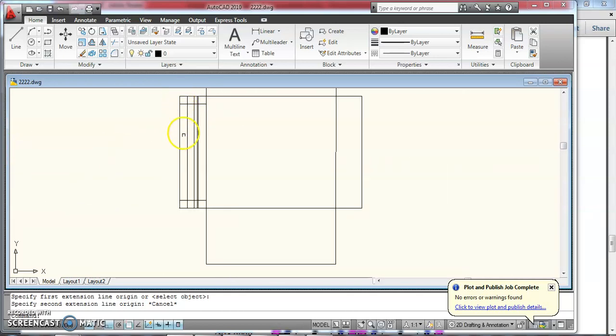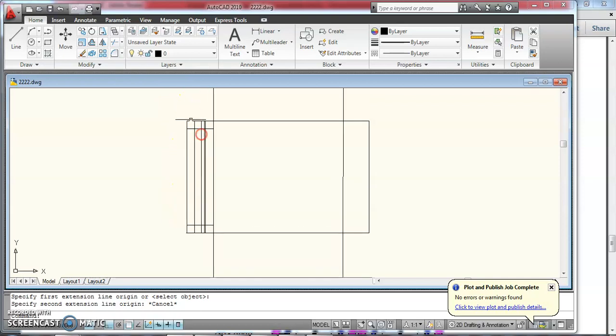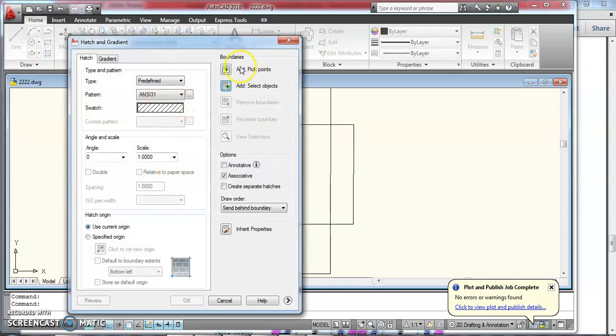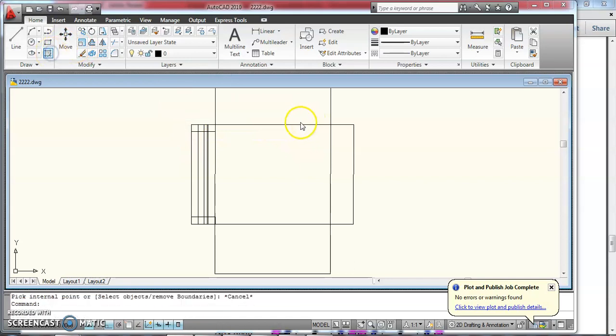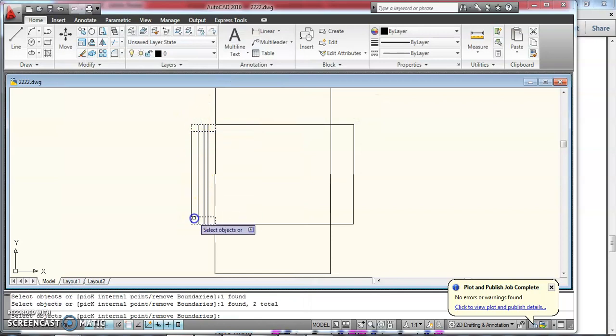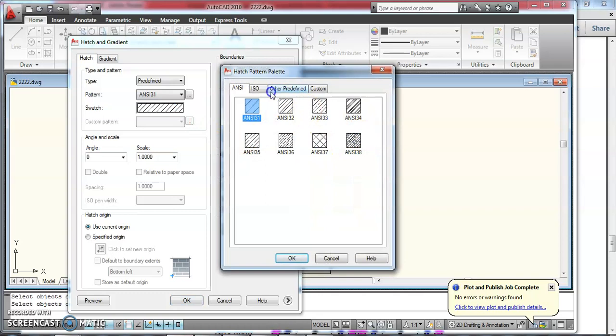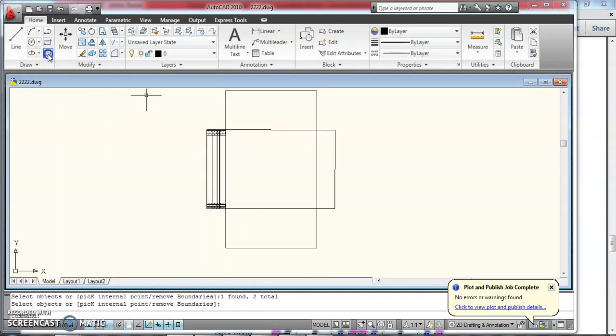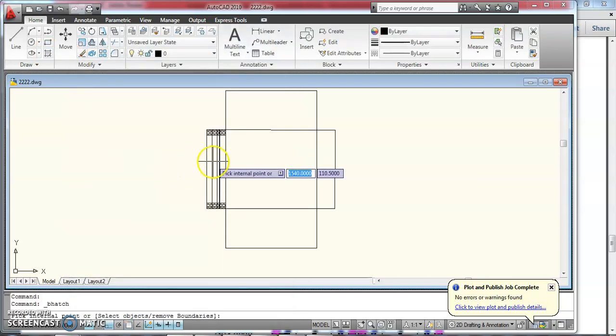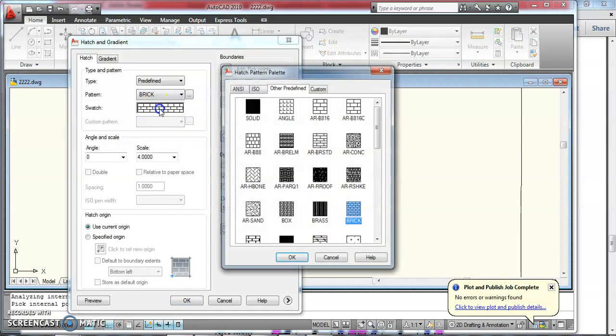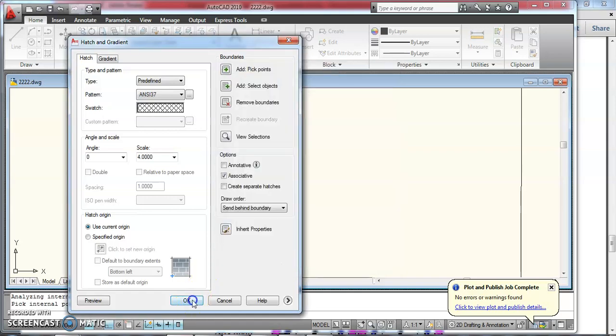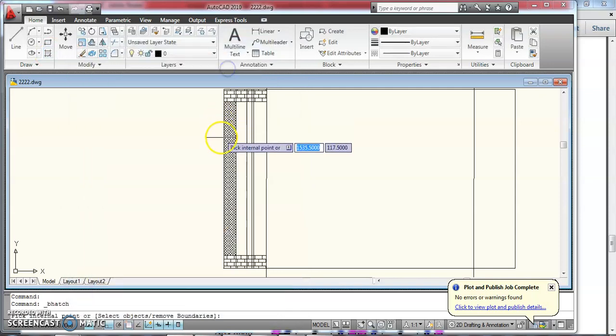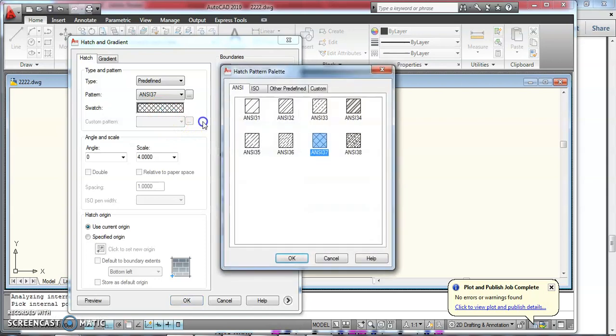Total core height is 50 cm. The middle winding height is 43 cm; 50 − 43 = 7, half is 3.5 cm above and below as insulation. Now I'll add hatches. Using 'Add: Select Objects', I select the box for the core and apply a Bricks hatch pattern. For the HV insulation I use a double-cross hatch pattern, and for LV insulation I use a single-cross hatch pattern. I add pick points for each region — HV, LV — and apply the respective hatch types.